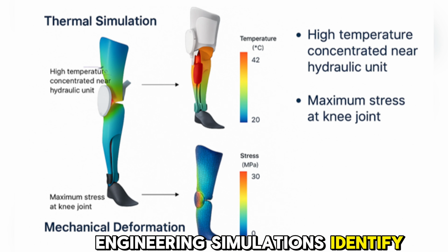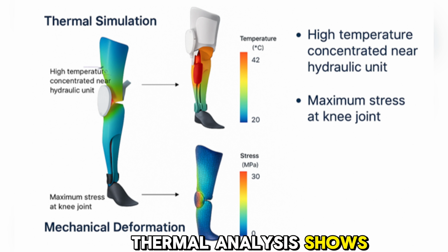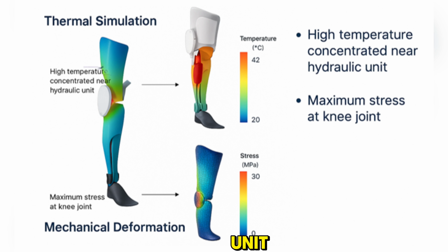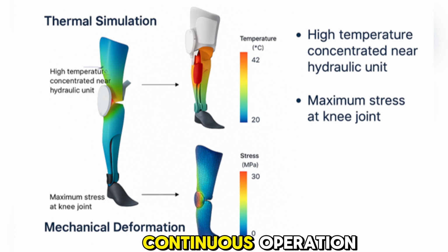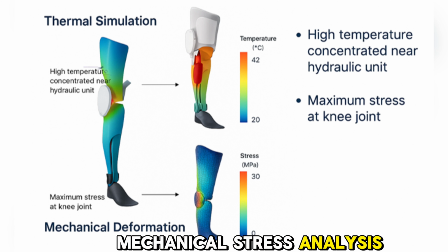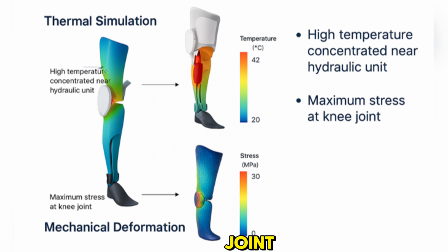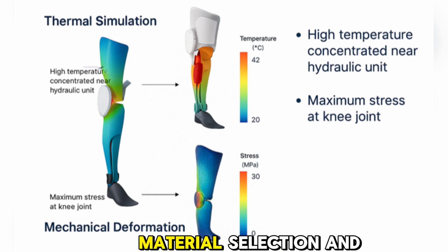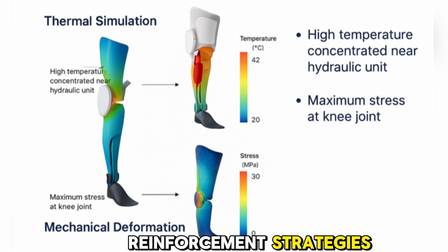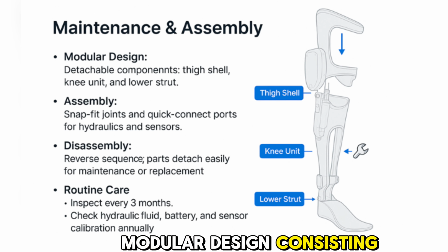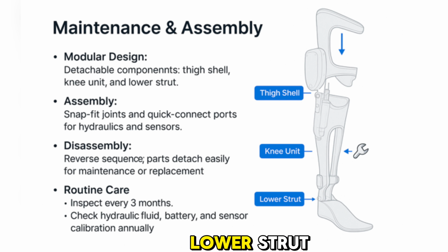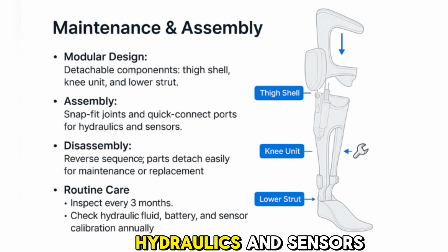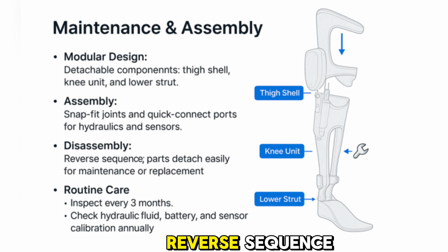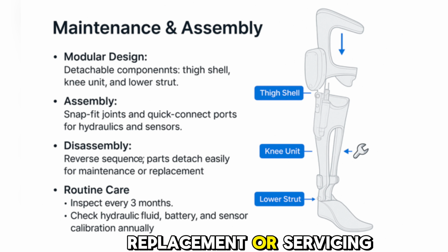Engineering simulations identify performance constraints. Thermal analysis shows maximum temperature concentration near the hydraulic unit with values up to 42 degrees under continuous operation. Mechanical stress analysis indicates maximum stress at the knee joint with values up to 30 MPa under peak load. These results inform material selection and reinforcement strategies. The device is constructed with a modular design consisting of a thigh shell, knee unit, and lower strut. Components are connected via snap-fit joints and quick-connect ports for hydraulics and sensors. Disassembly follows the reverse sequence, allowing for part replacement or servicing.